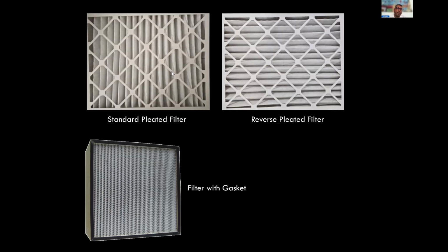Another thing that's very, very popular and becoming even more popular is putting gaskets on the filters. The filter on the bottom we can see here has a neoprene gasket on it. What that does is it helps seal the air, seal the space, excuse me, around the filter to allow for less bypass. Now, I have yet to see a filter that can give you zero bypass. However, we can get pretty close by putting a good quality gasket. So the pleat orientation, putting gaskets, and in some cases, adding clips onto the filters to help fit them in better, have proven great success in eliminating bypass.